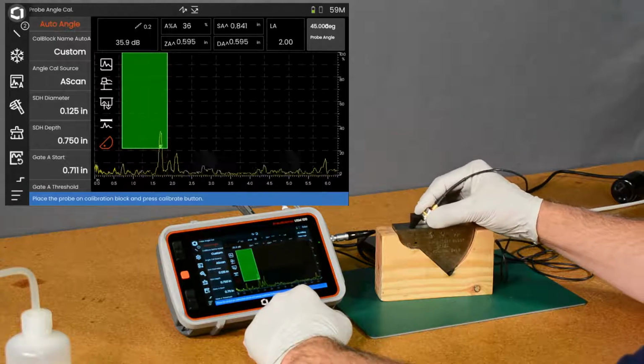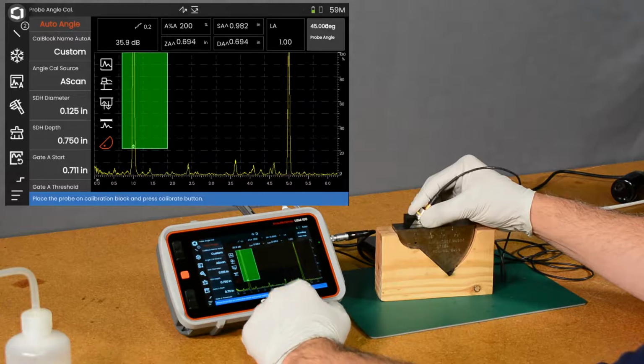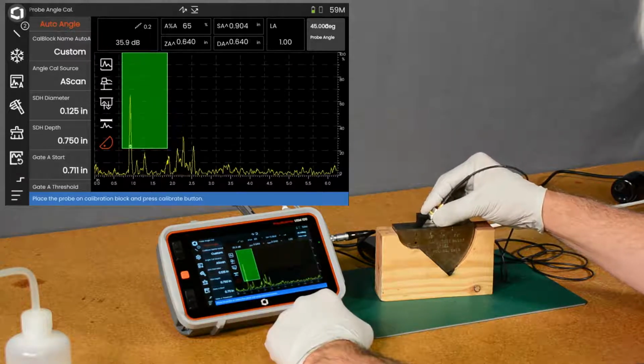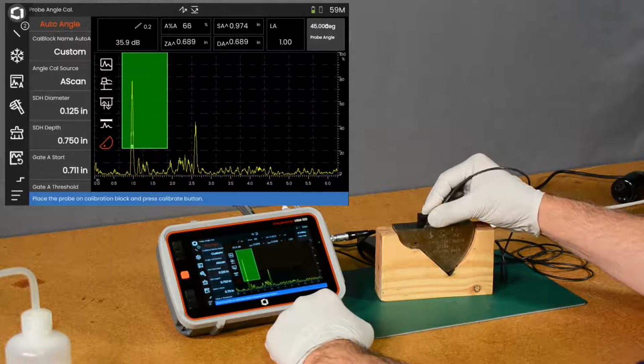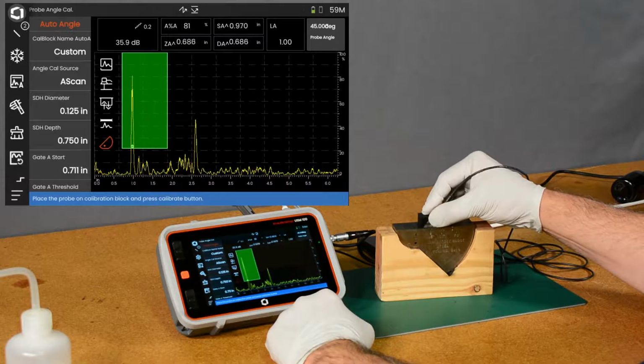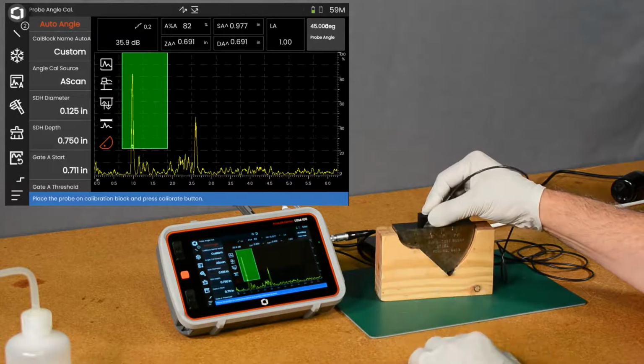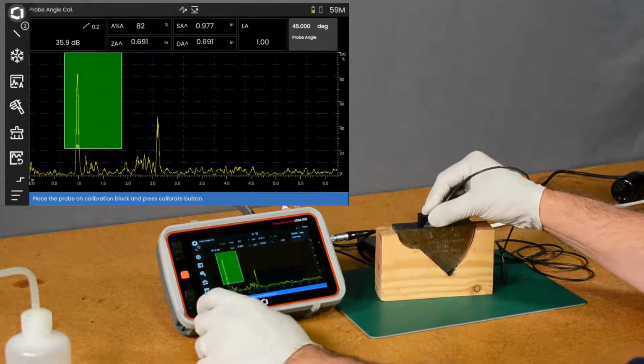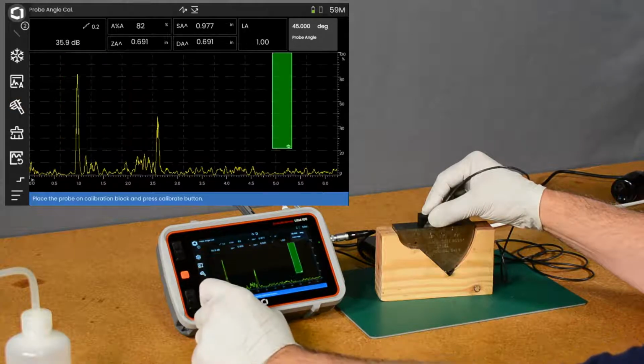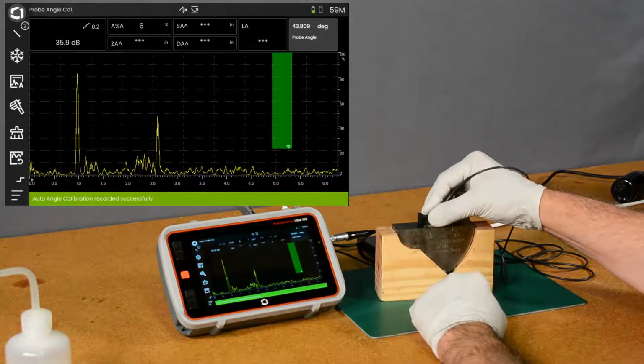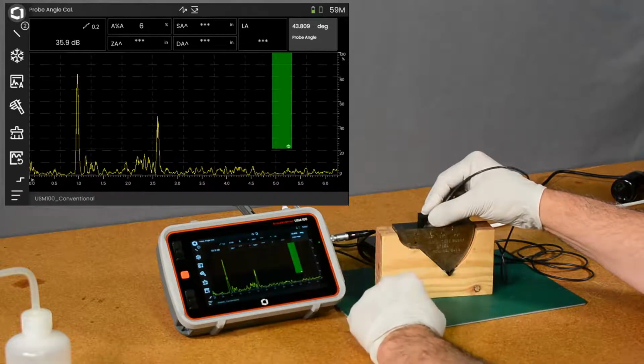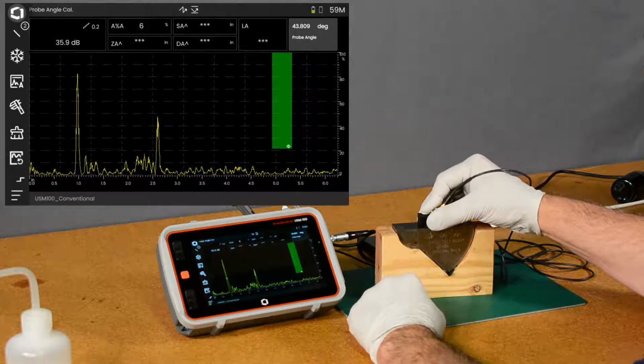Come in here. So if I come over to this index mark, there's our 1 inch radius. If I slide back to the 45-degree marks, I can peak up on that side drilled hole. I need to slide forward and backwards to find the exact peak. And that can be a little fidgety, you know, for those of you who have done this calibration many times on other instruments, other blocks, it's a little fidgety scrubbing your probe around. But once you've found your location, your peak, go ahead and hit cal. And it calibrated, and it's determined that based on that echo that we showed it, our angle is 43.8 degrees.